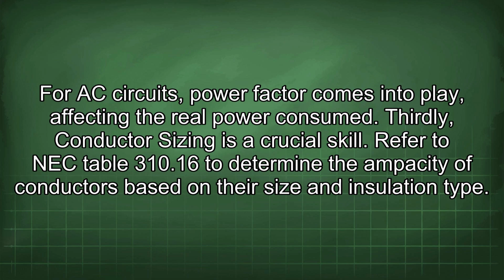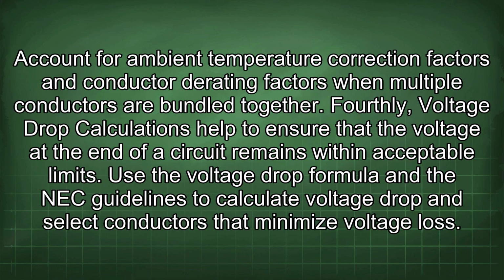Thirdly, conductor sizing is a crucial skill. Refer to NEC Table 310.16 to determine the ampacity of conductors based on their size and insulation type. Account for ambient temperature correction factors and conductor derating factors when multiple conductors are bundled together. Fourthly, voltage drop calculations help to ensure that the voltage at the end of a circuit remains within acceptable limits. Use the voltage drop formula and the NEC guidelines to calculate voltage drop and select conductors that minimize voltage loss.